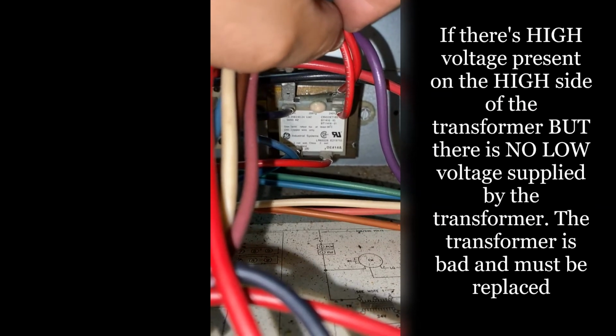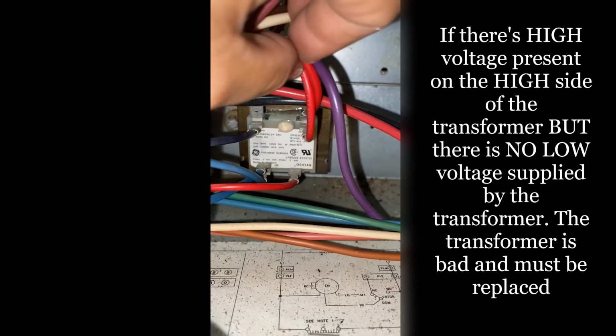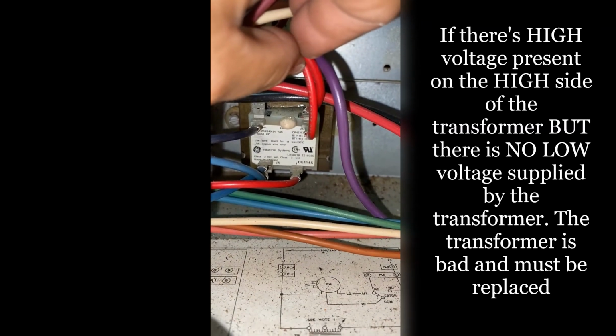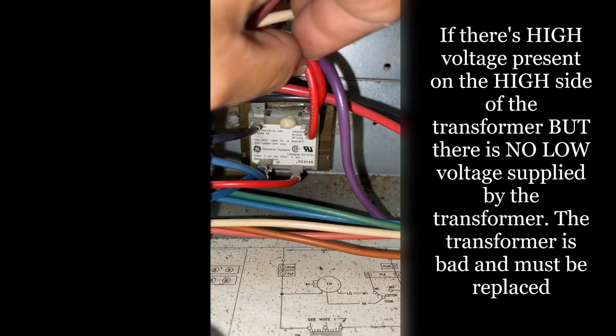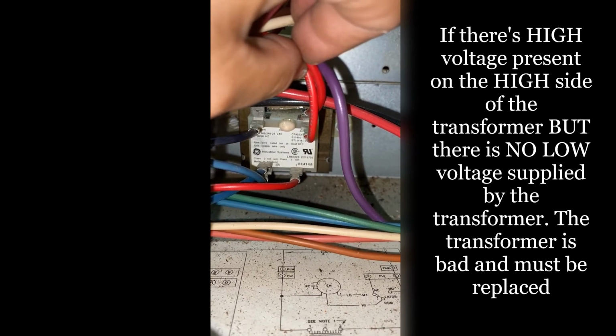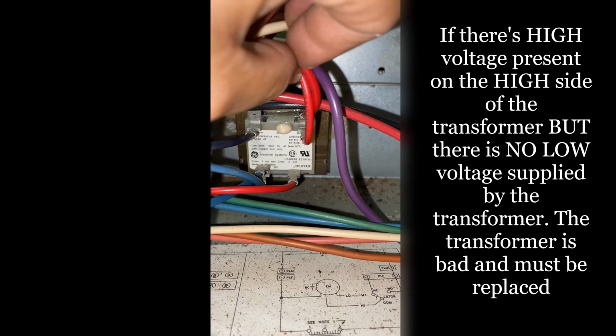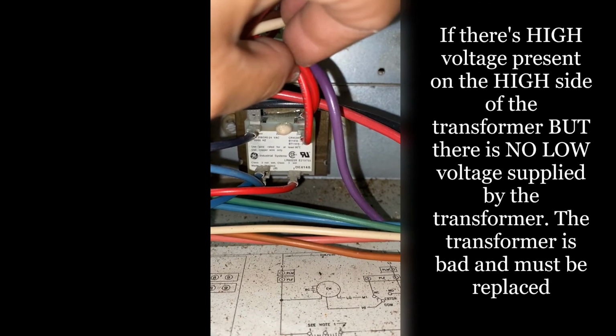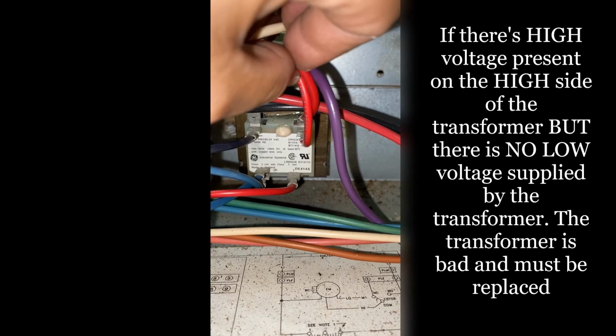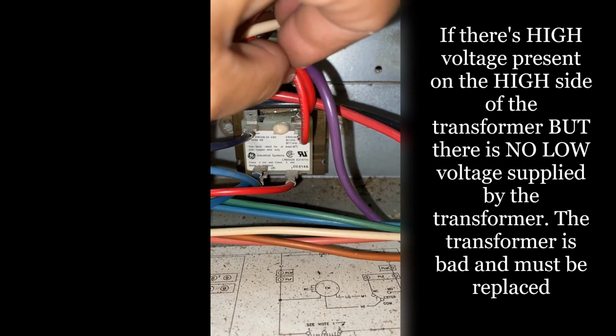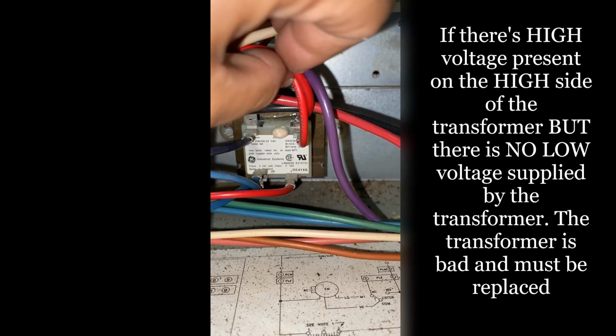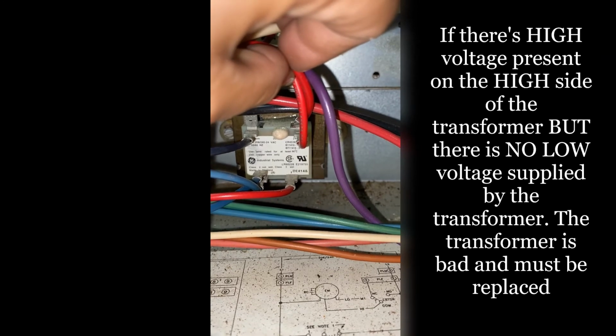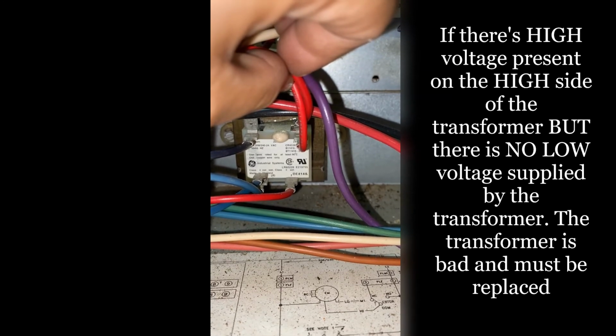Then the other two terminals at the bottom, let's see if I can get it closer here. That's your 24 volts. You can kind of see it right there next to the blue wire. It says 24 volts. And usually your red wire is the one feeding out. It's not DC, but it's directional. One is a common and one is the voltage. If you check between those two, you should have at least 24 volts. If you don't, and you have high voltage, then your transformer is bad and needs to be replaced.